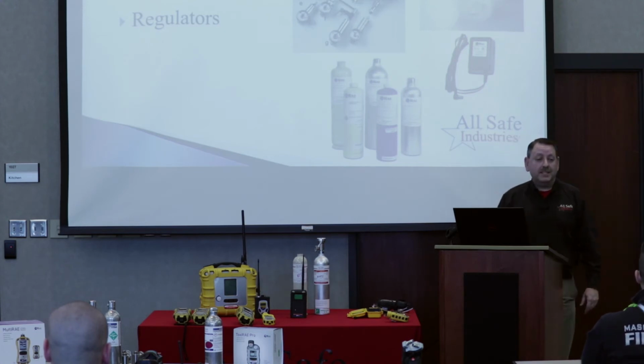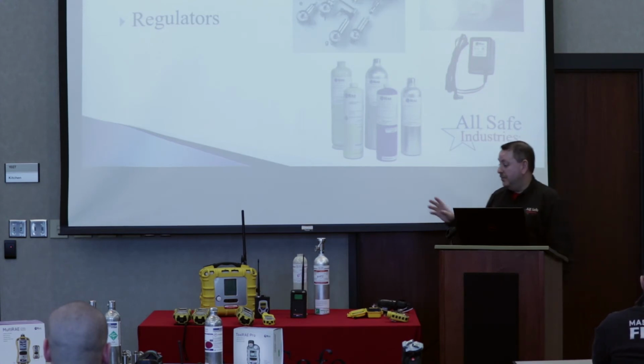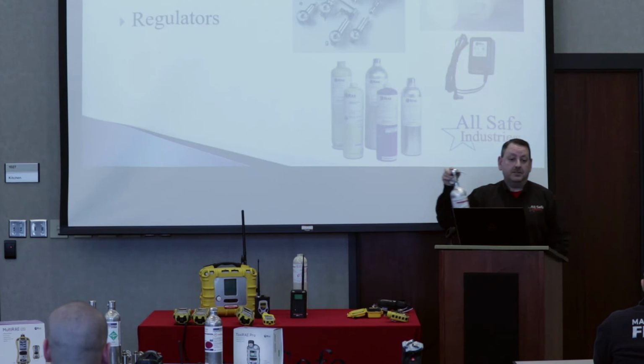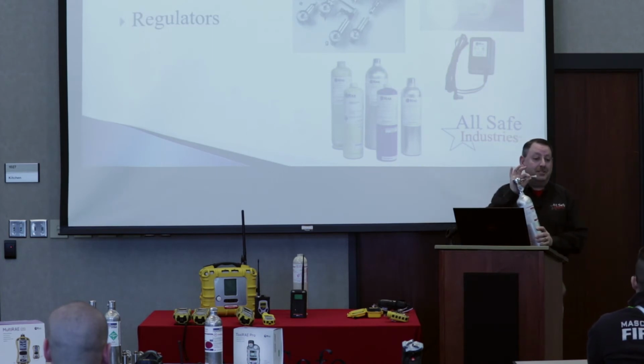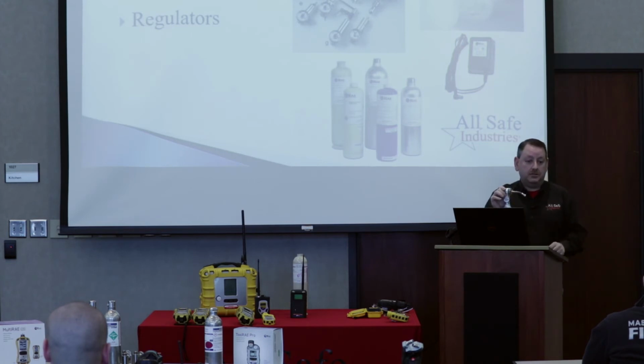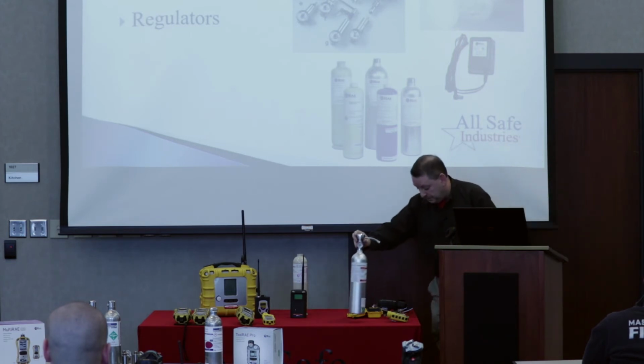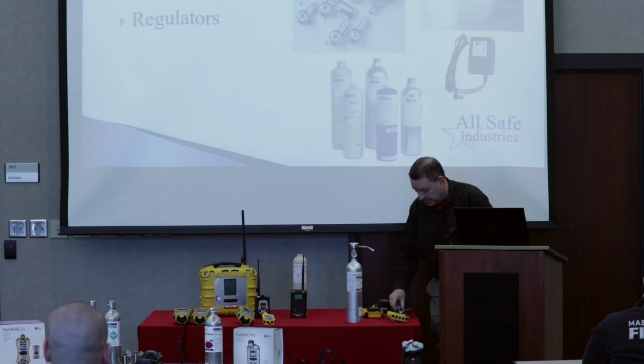And then, as important as the calibration gas is, the regulator that's on the cylinder, okay? And the little piece of tubing. You would be surprised how 50 cents worth of tubing can stop you from using your gas meters if you have no way to get the gas out of the cylinder and to the sensors in the instrument. So we'll just talk real briefly about a couple different types of regulators.